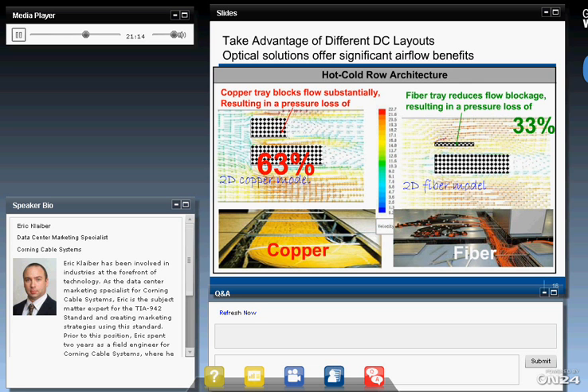So here's a better look at a raised floor environment. On the left-hand side is a depiction of copper cabling. This is a 2D copper model, and the right one is a 2D fiber model. What we're showing here is air velocity, so the redder the arrows, the higher the velocity. The fiber tray on the right has the amount of cabling needed to facilitate what the left tray with the copper is doing. So we're not sacrificing port counts. We're not sacrificing bandwidth. In fact, we're probably increasing bandwidth. But what we see is the amount of air blockage that the copper cabling can cause.